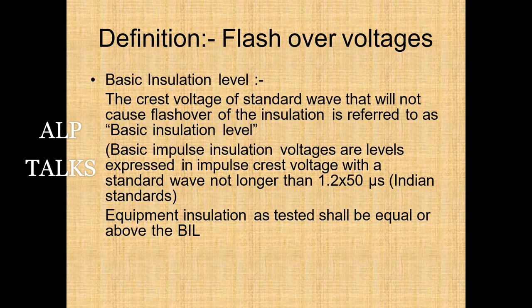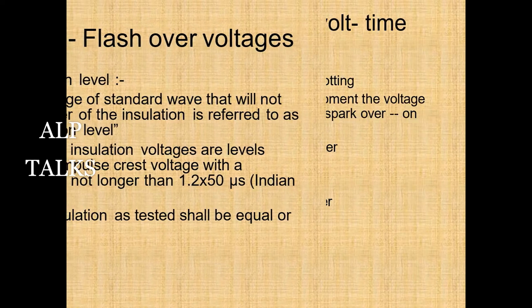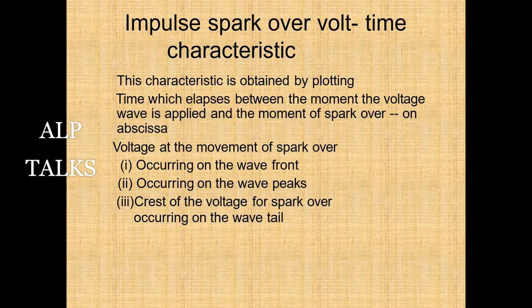Basic Insulation Level (BIL) is the crest voltage of a standard impulse wave that will not cause flashover of the insulation. BIL is expressed as an impulse crest voltage with a standard wave not longer than 1.2/50 microseconds. Equipment insulation strength as tested shall be equal to or above BIL.